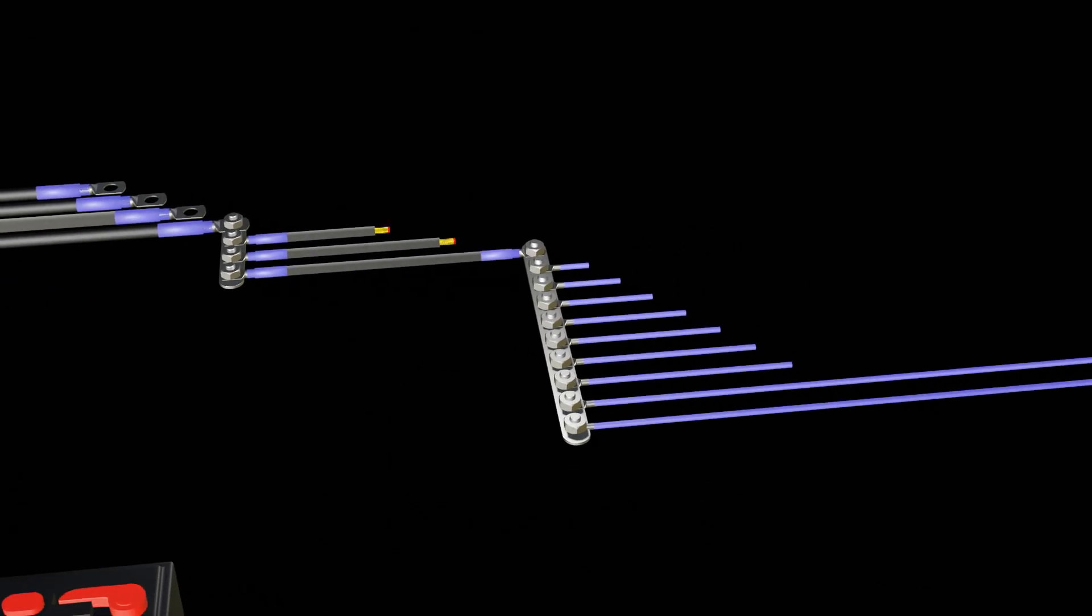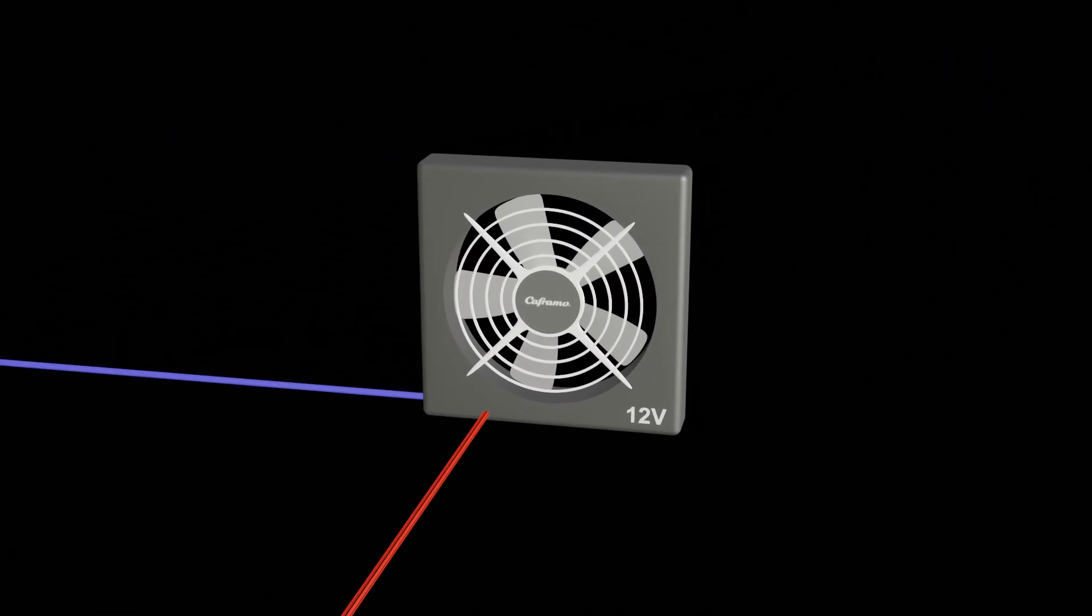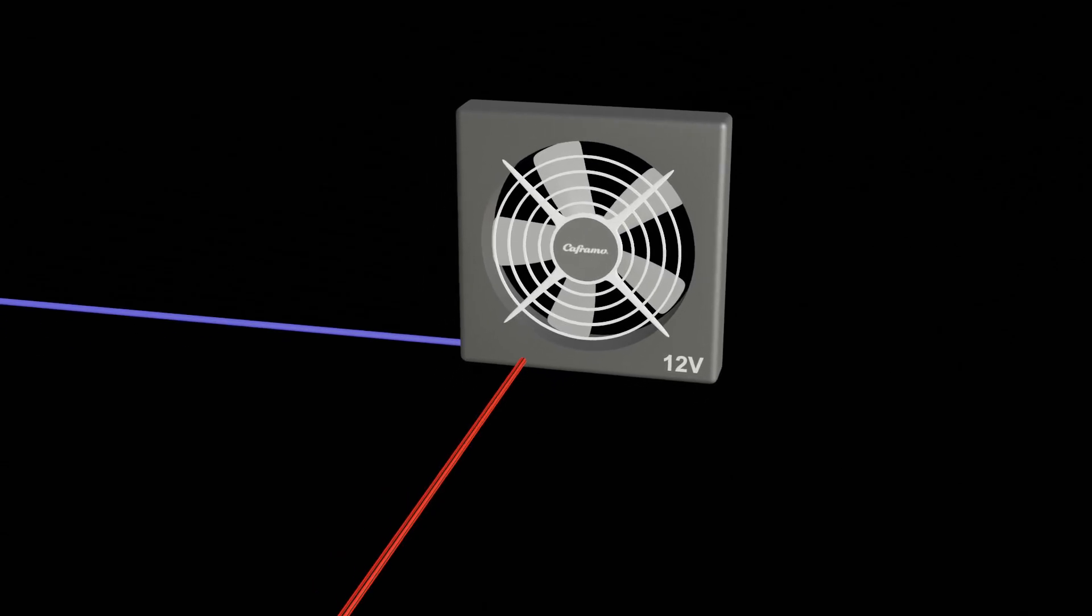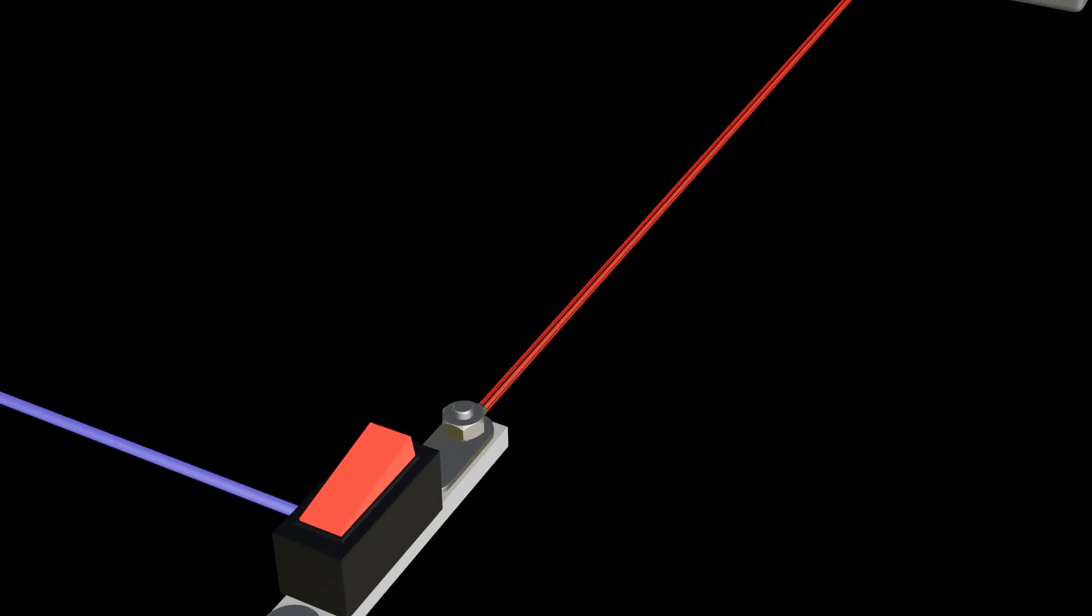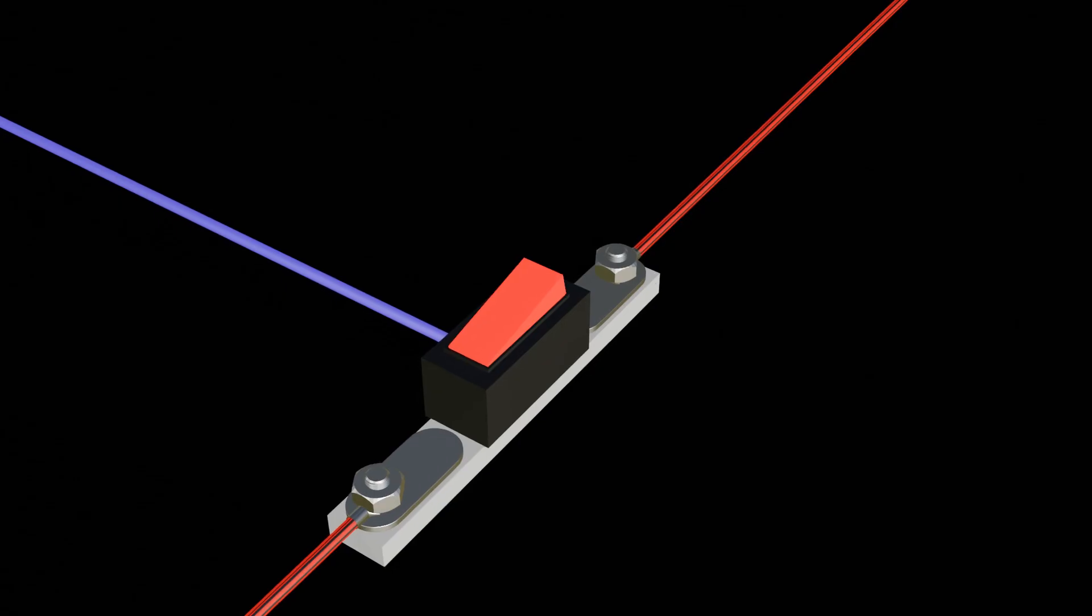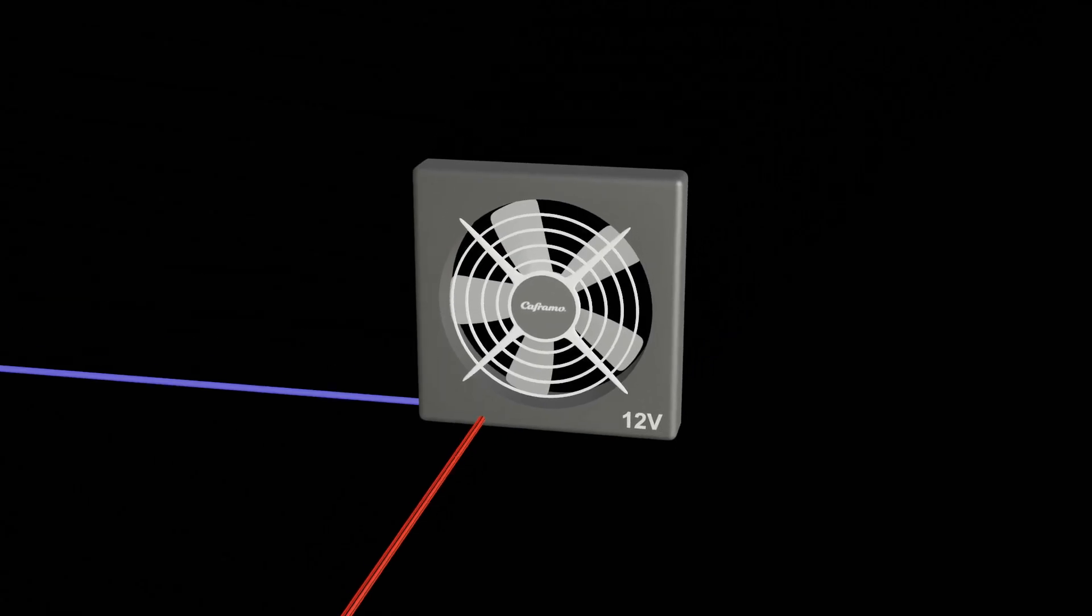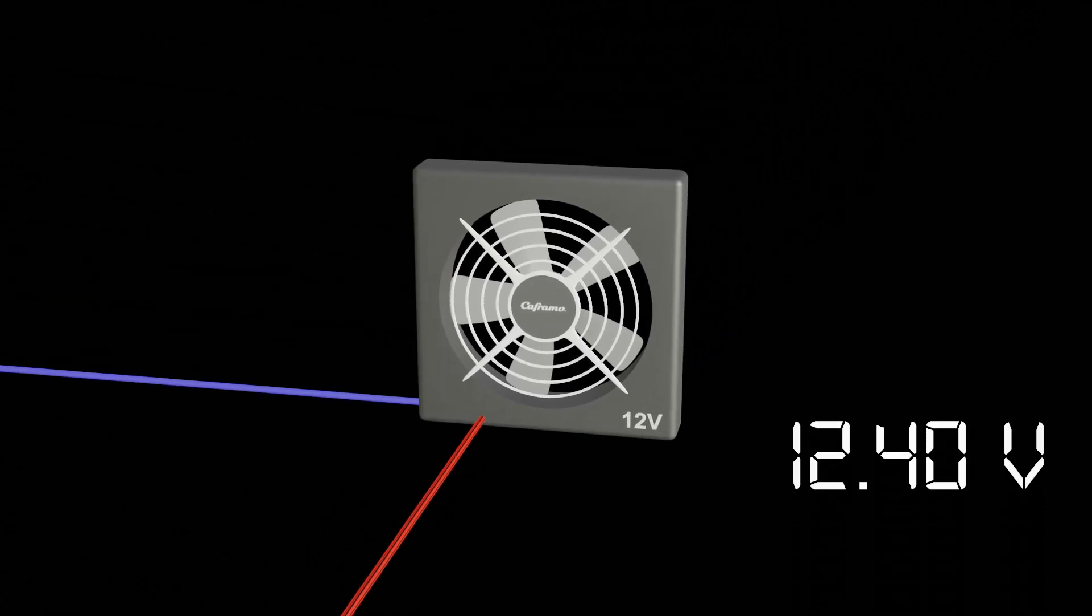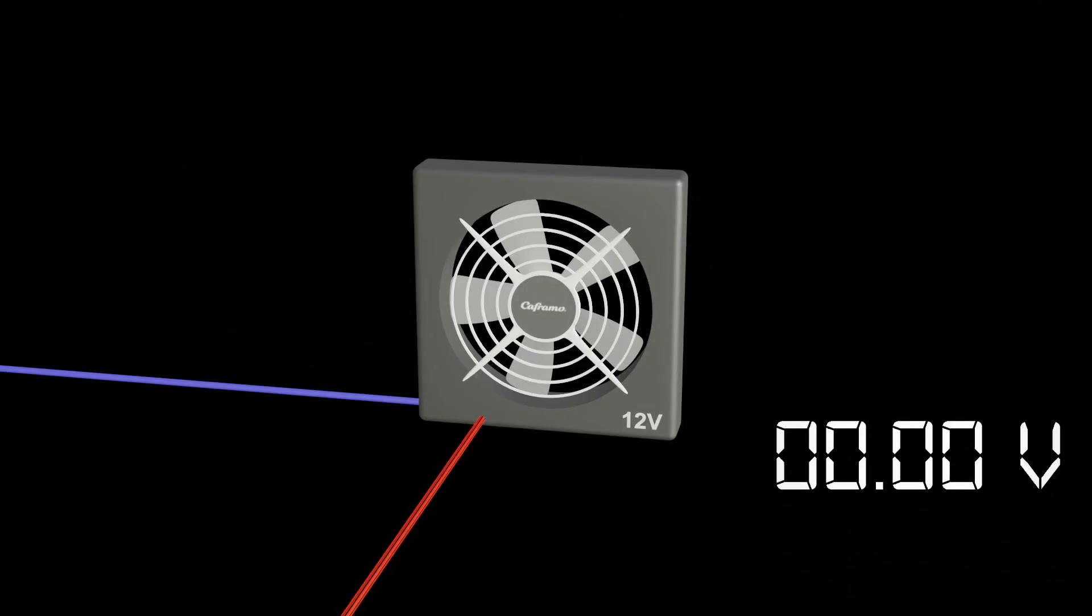If the fan stops working, we have to follow the flow and troubleshoot from the device back. First, we check the switch. If the switch has power, then the issue is either in the wiring to the fan or the fan itself. Using a multimeter, we can check if any current is flowing to the fan. If it shows as good, then the problem is with the fan. If the voltage shows as zero, then check the wiring.